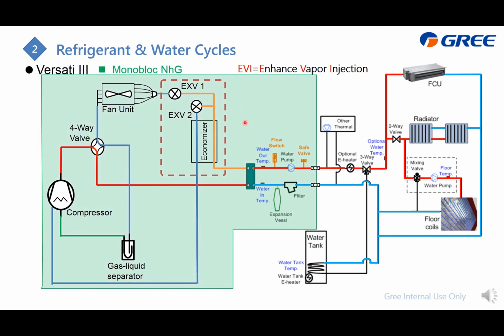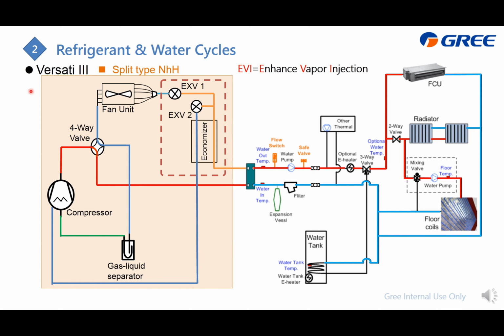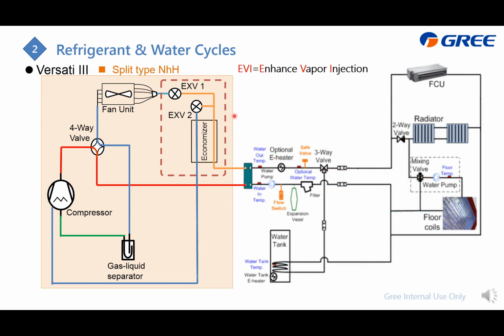And when we combine the hydro box with the outdoor unit, it will become the monoblock NHG series. When we developed the VERSATI3 split type, we just cut this off, and then this part is the split type NHH series. But this hydro box, we made a change to it, which is to make this three-way valve built in, also to make it easier for you to install. So on site, you just need to install these three, and here is how the water flows.